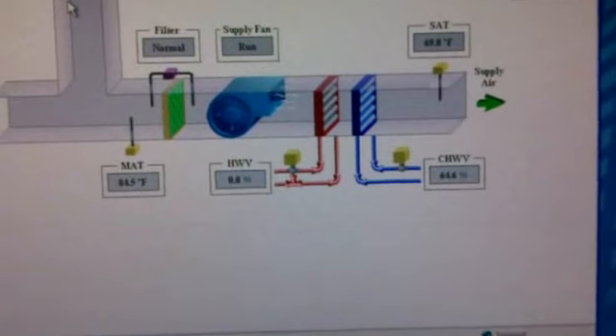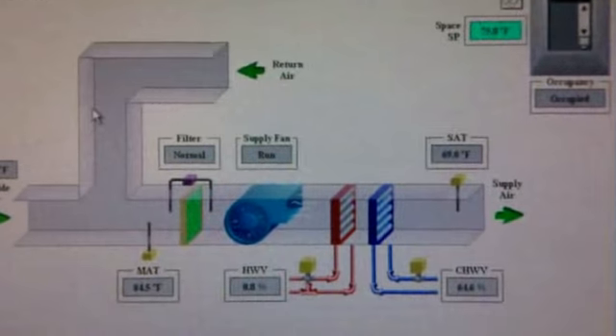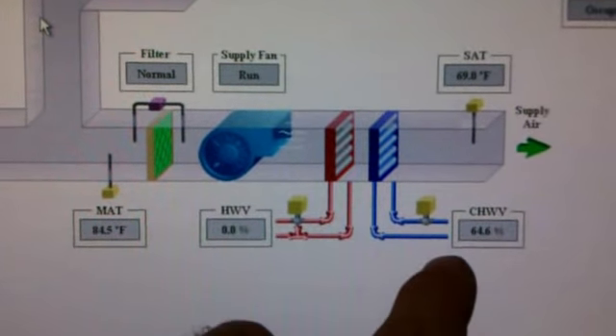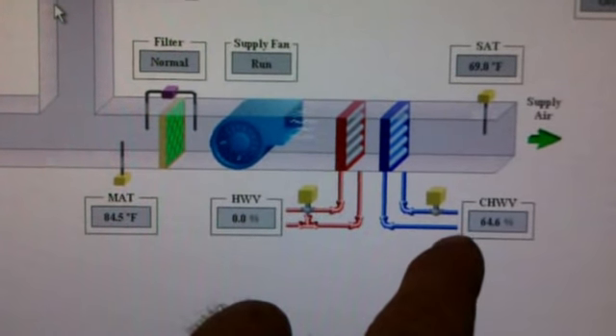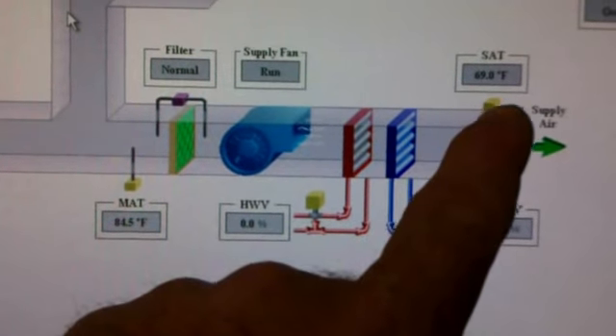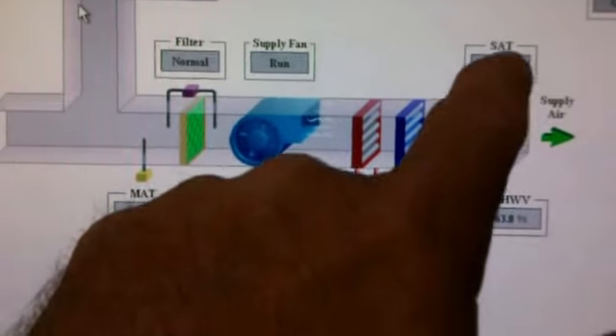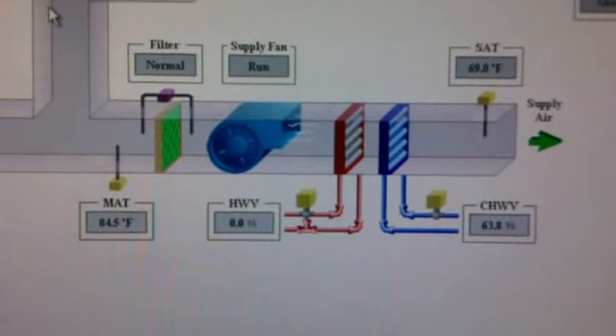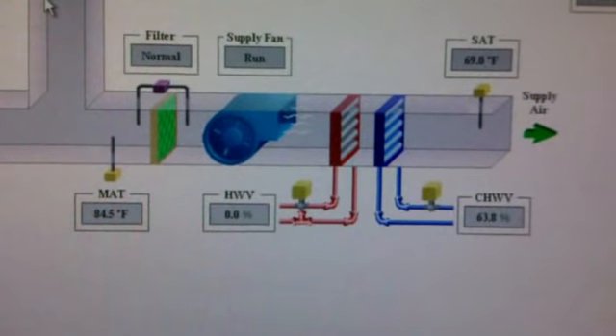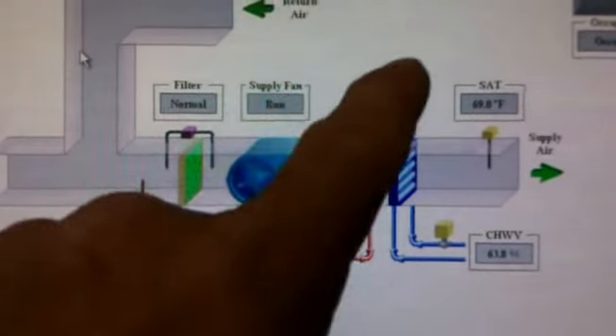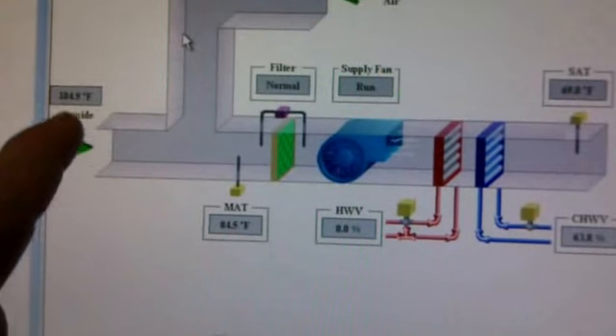So it's working pretty good to maintain steady. See, right now the valve is opened up a little more. It's at 64.6%. It's still putting out about 69 degrees. That's all it takes. If a lot of people came in that room, then obviously you'd have to blow colder air than 69 out the vents to maintain, as well as maintain the increase in outdoor temperature.